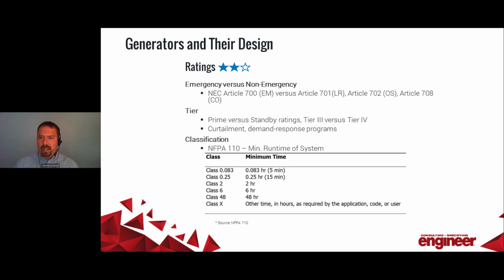And then you've also got tier ratings, right? So if you're using your generator for prime power production, so if you're using the generator more often than not to generate the majority of the power for the campus or the facility, that would be a prime power installation, whereas a standby rating would be, if you've got the generator only there for use in an emergency situation where normal power has failed and you need to back up emergency systems, that would be a standby rating. Tier 3 applies to standby, and a Tier 4 applies to prime, and those are EPA emission ratings. So the generator just needs to be rated applicable to what you're using it for.